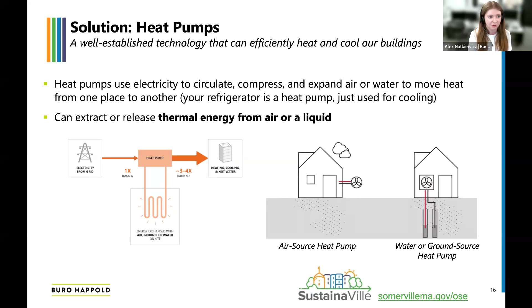When we think about how efficient a heating or cooling system is, we basically want to look at the amount of energy needed to meet the temperature you want for your space. Say we're in a cold snap—it's pretty cold right now here in Somerville—and I want to heat my home to 68 degrees Fahrenheit, which is standard for a living room. An air source heat pump will need to take 0-degree air, or whatever temperature it is outside, and bring it up to 68 degrees. A ground source heat pump instead takes temperature from the ground, which is pretty consistently 55 degrees throughout the year, and brings that to 68 degrees. It's probably a lot easier to step up 13 degrees from the ground than the full difference from the outside air.